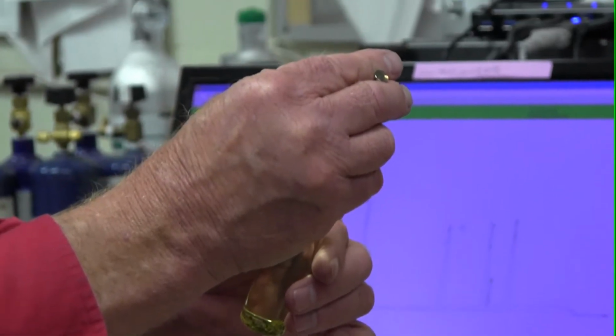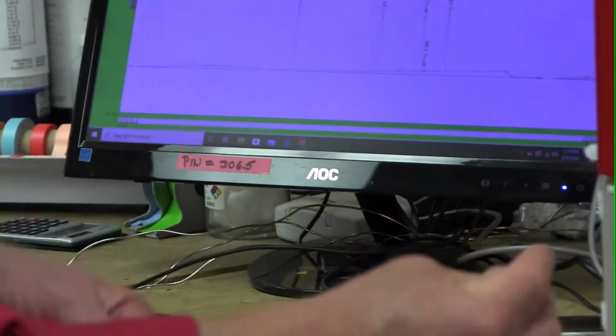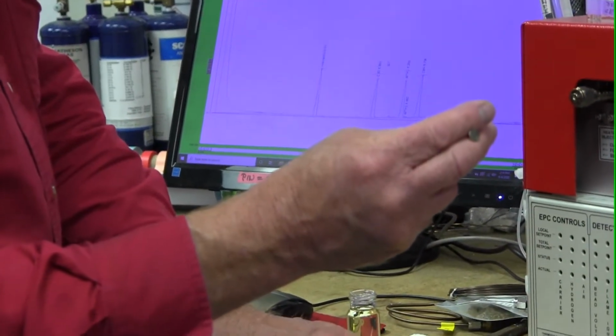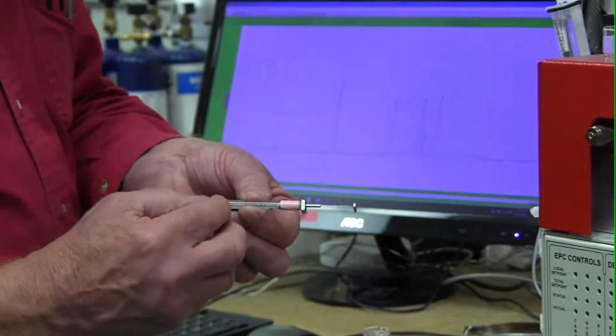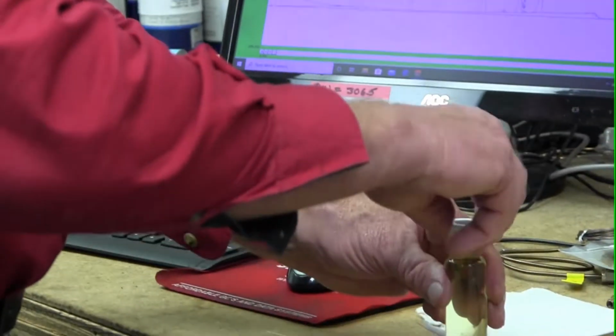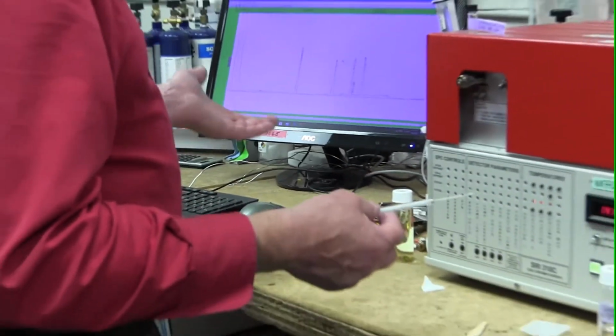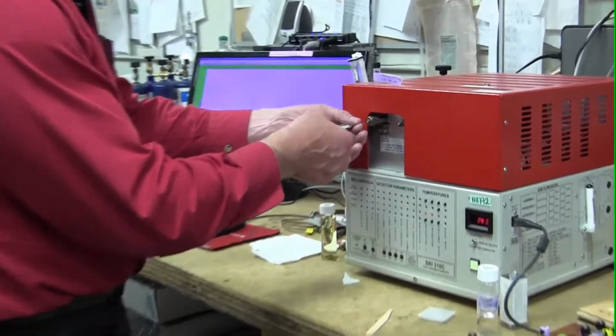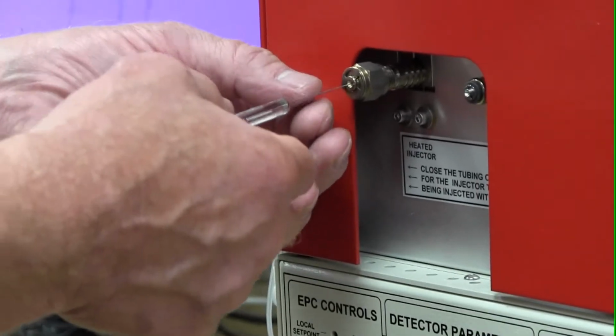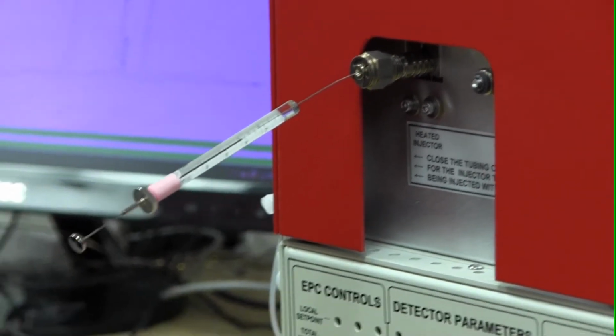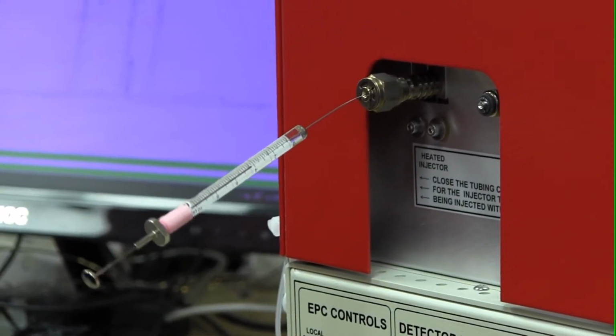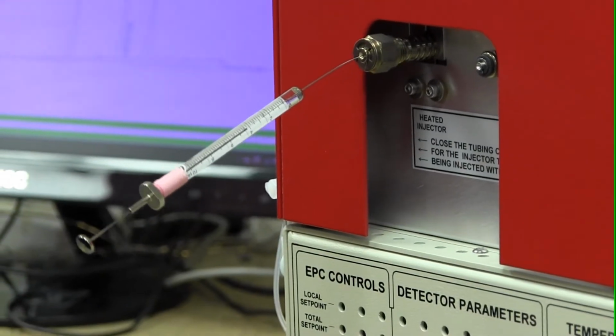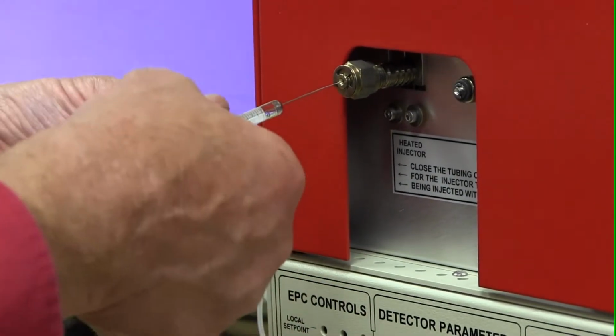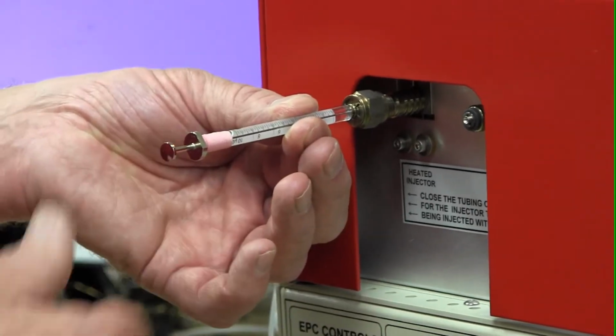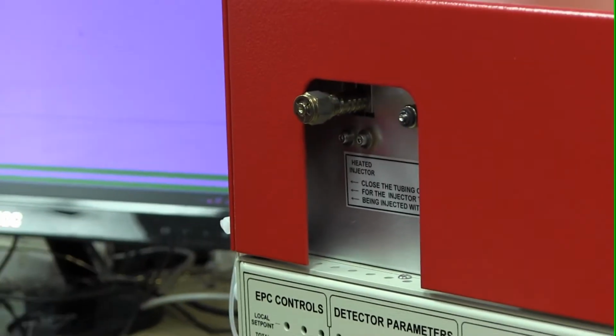So you pull it up to the 1 mark, just like I did before, and then back to the 4 mark so that I can actually see the 1.5 microliters of liquid in the syringe. Take a look around, no rush. Poise my syringe up against the rubber septum, but being careful not to go through the septum. Just poising it there so I don't have to hunt and peck when I finally decide I'm ready to inject. And then when I am, I hit the start button first, immediately ram it in up to the hilt, depress the plunger, and then pull it out.